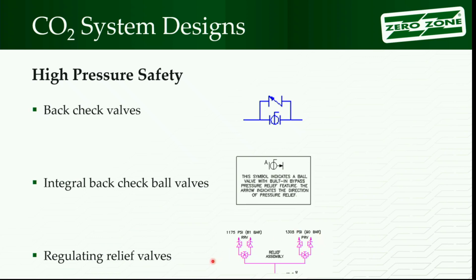On the safety valve standpoint, if you have one leaking, you need to change it out then. And I don't know if you're all familiar with the three-way valves on there. The three-way valves are designed so that you're either on one port or the other port. Some of the valves, I think you can be in a middle position, but you do not want to operate those in the middle position. We had a customer ordering two safety valves because he had a release, and we asked him, well, what do you need two safety valves for? He said, I had a release, they both went off. And we're like, okay, not really. That valve should have been isolating one side or the other.